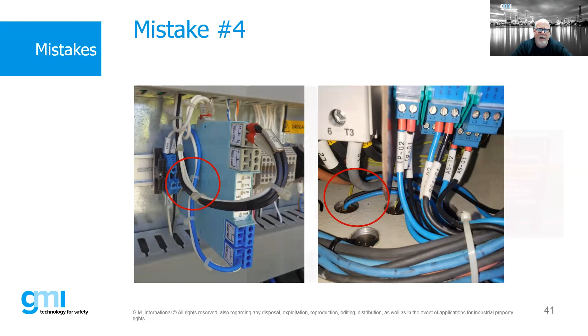Mistake number 5 is actually using a used certified product. And I apologize because this label is a little bit difficult to see, but what we see at the very back of this certificate is actually a U. And that means that this manufacturer supplied an empty enclosure. The client, in this particular instance, installed certified terminal blocks. However, this is not an assembly certified product. So therefore, this was rejected by the client. Even though it looks fantastic, it's done properly, it's not an assembly certified product.